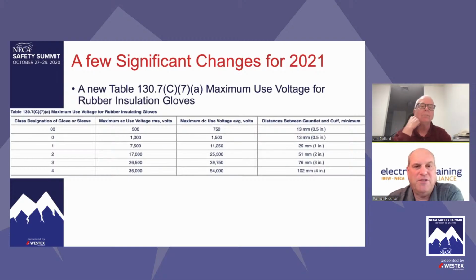Now, the thing that might not be as obvious, the next column over would be for DC. The far right is what most people don't know: there has to be a distance between my rubber insulating glove and my leather protector, because the leather protector obviously is not insulated and the rubber insulating glove is. So you've got to have a gap there. That's what they're showing you for class 00. You need at least a ½ inch gap between the insulation and the conductive material, and then all the way up through class 4, you need 4 inches. So they call it a moat around the castle. You need that separation. And the other thing is, you don't want to see too much exposed either at the same time. So this is a great tool.